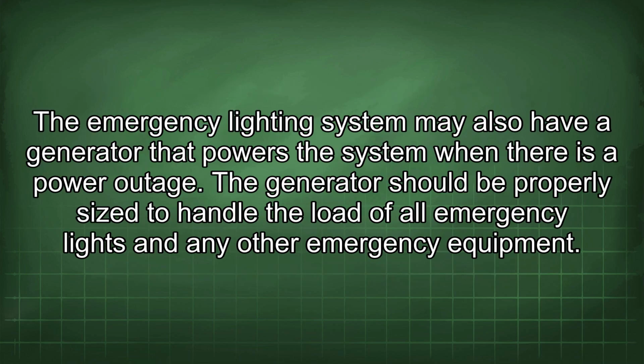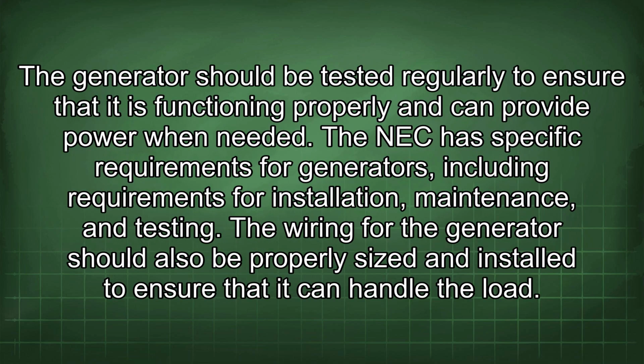It is important to consider these interconnections to ensure that both systems function properly and do not interfere with each other. The emergency lighting system may also have a generator that powers the system when there is a power outage. The generator should be properly sized to handle the load of all emergency lights and any other emergency equipment. The generator should be tested regularly to ensure that it is functioning properly and can provide power when needed. The NEC has specific requirements for generators, including requirements for installation, maintenance, and testing. The wiring for the generator should also be properly sized and installed to ensure that it can handle the load.